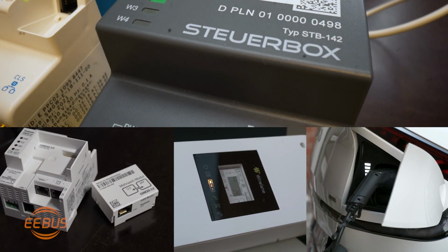To integrate flexible loads such as EVs or heat pumps into the overall power grid, the grid operator must be able to limit the power consumption at the grid connection point of a building in times of impending grid overload scenarios. EEBUS has developed a communication interface for every single component and device that is involved in the entire process chain, which enables the transmission of a signal from the grid operator to the end device within a few seconds. We call this signal power limitation.